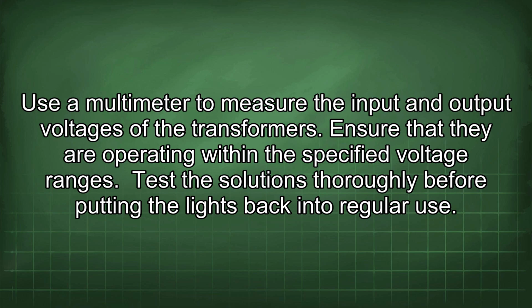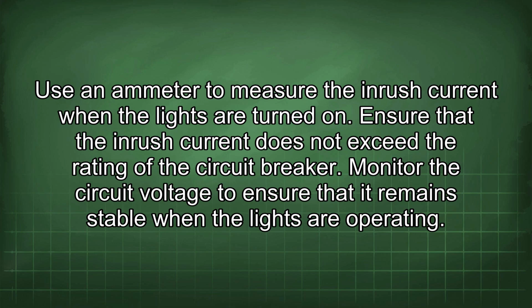Test the solutions thoroughly before putting the lights back into regular use. Use an ammeter to measure the inrush current when the lights are turned on. Ensure that the inrush current does not exceed the rating of the circuit breaker. Monitor the circuit voltage to ensure that it remains stable when the lights are operating.